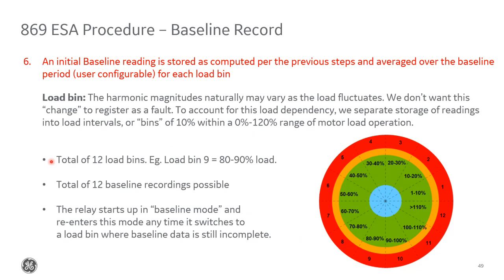values for subsequent monitoring. We do this baselining separately for what we call each load bin. A load bin is defined as 10% chunks of the operating load, basically what you see in this pie here. So for example, if you're at 75% load, you'd be operating in load bin 8.